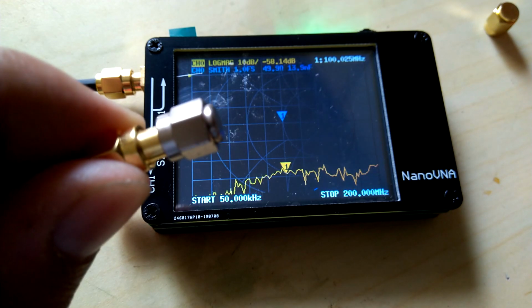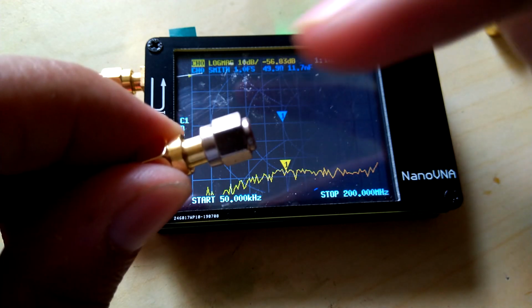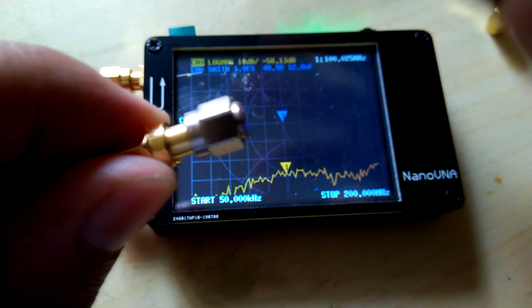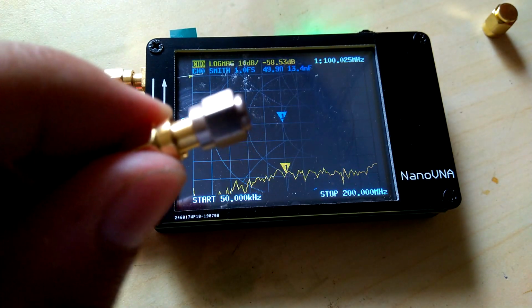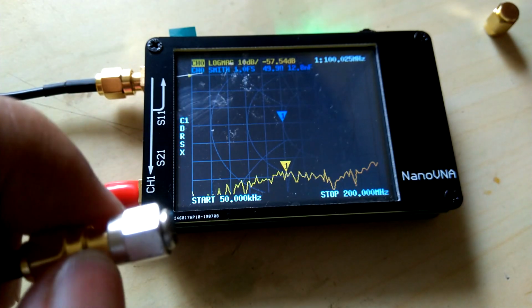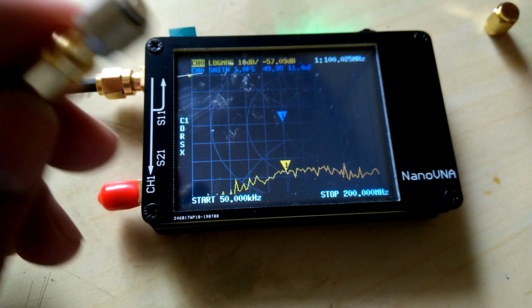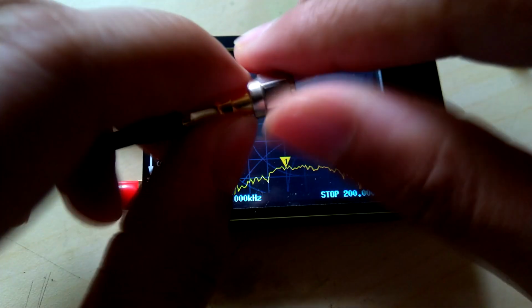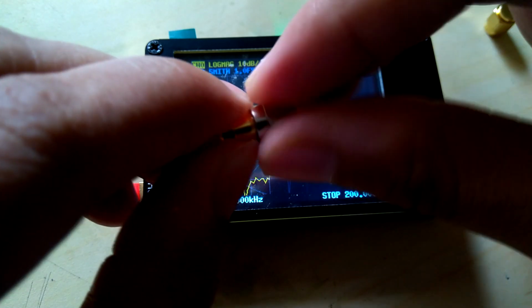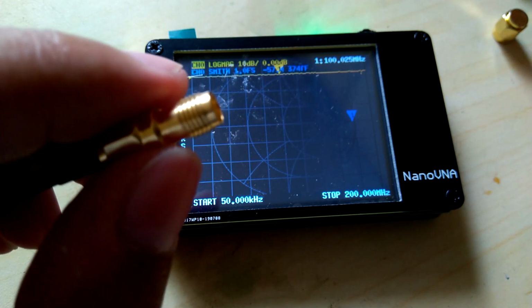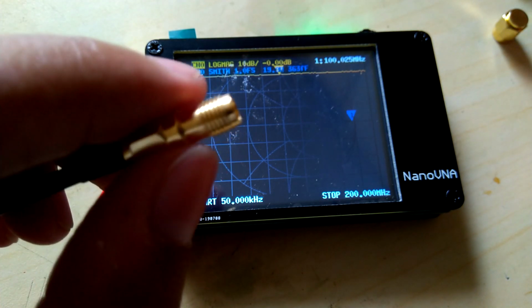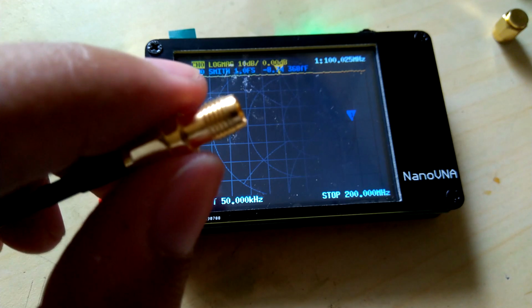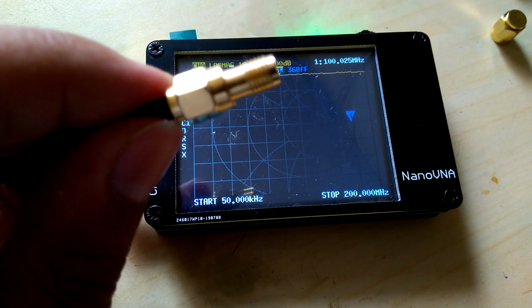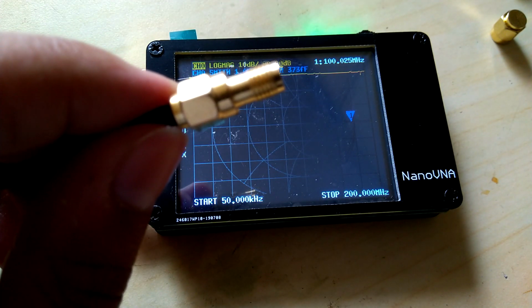Oh, has it come in the middle? Yes, it has, which is indicative of a very good quality load. It may not be very good quality for high frequencies, but for the frequency range that we are looking at, it doesn't really matter. It's a good load in my opinion. And there we are back at the right side, an open circuit. And that's how we calibrate this VNA for one port measurements.